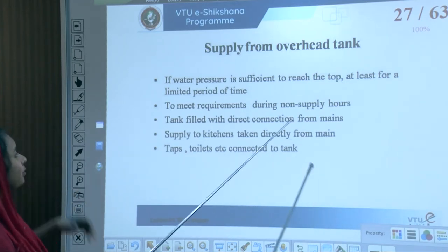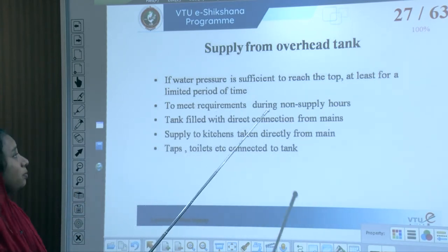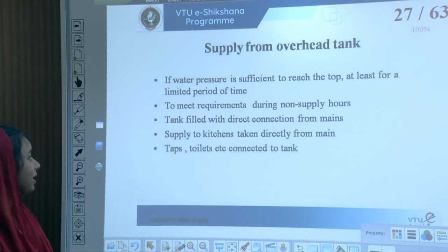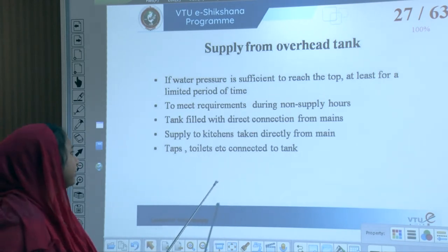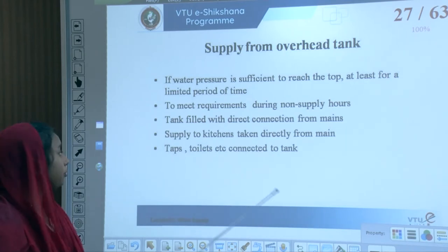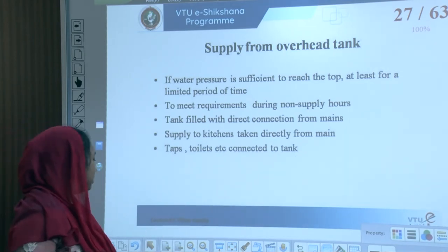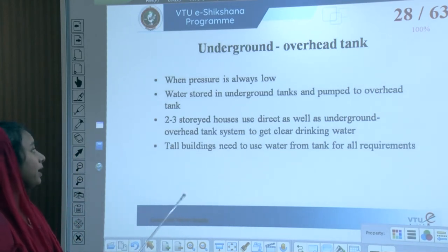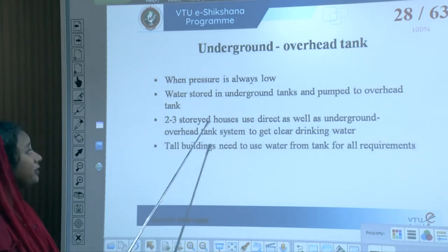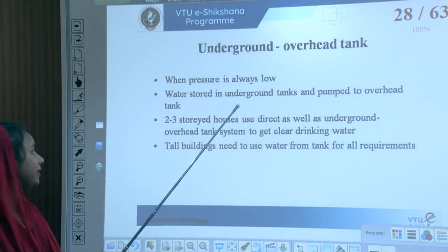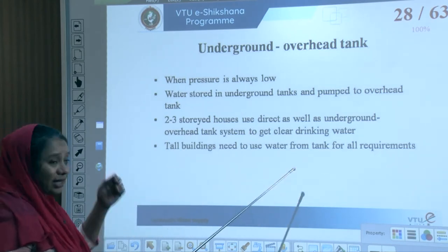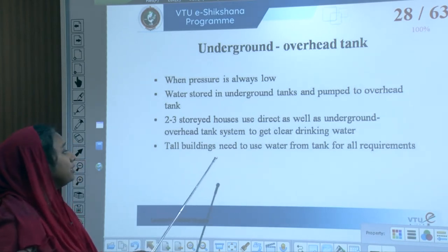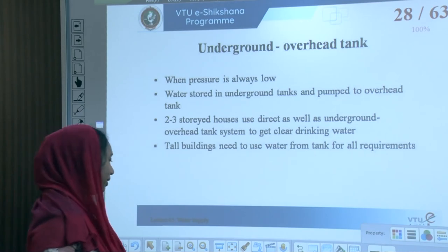For overhead tank supply: if water pressure is sufficient to reach the top for a limited period, the tank is filled with a direct connection from the mains. Supply to kitchens is taken directly from the main; taps and toilets are connected to the tank. When water pressure is low, water is stored in underground tanks and pumped to the overhead tank. Tall buildings need to use water from the tank for all their requirements.